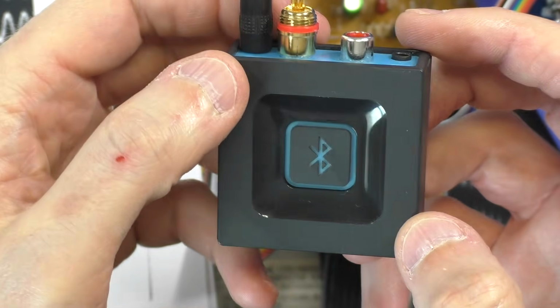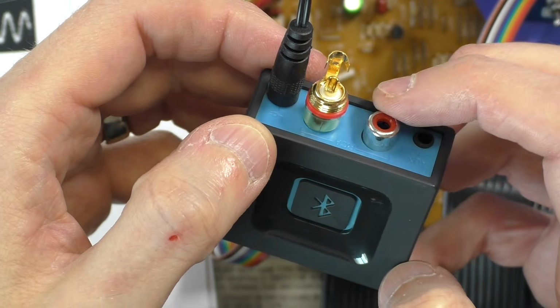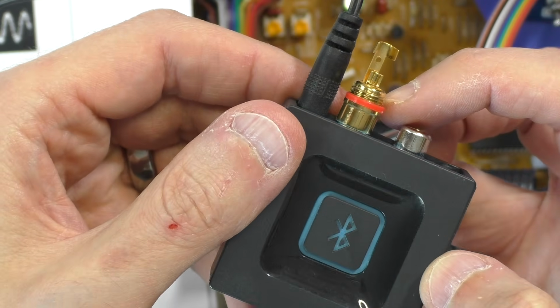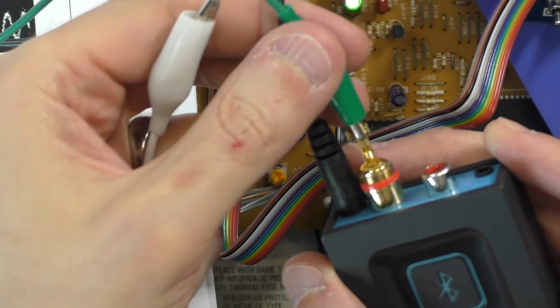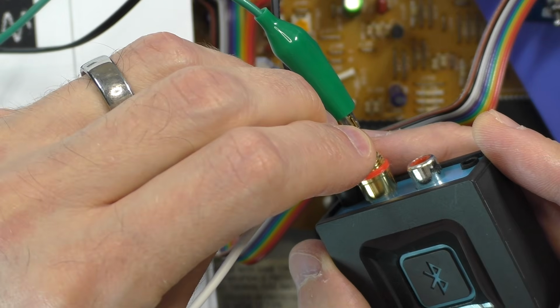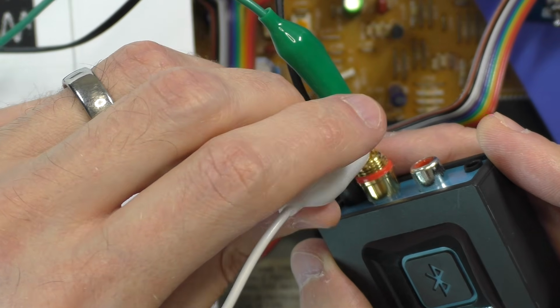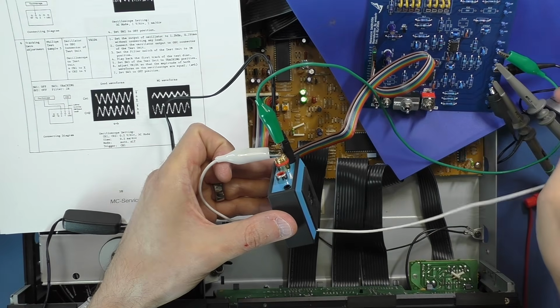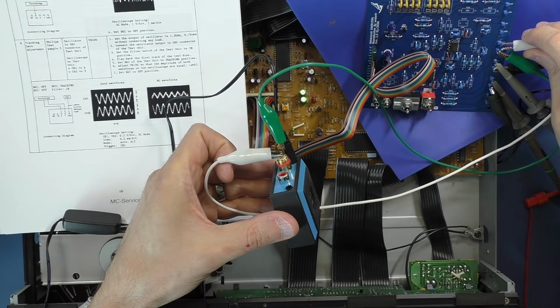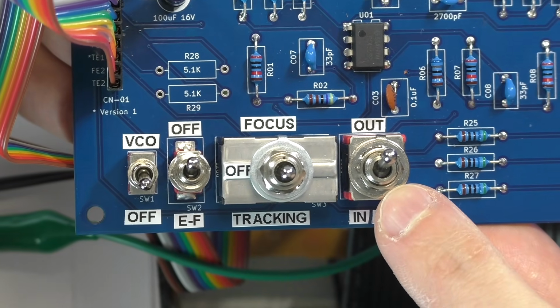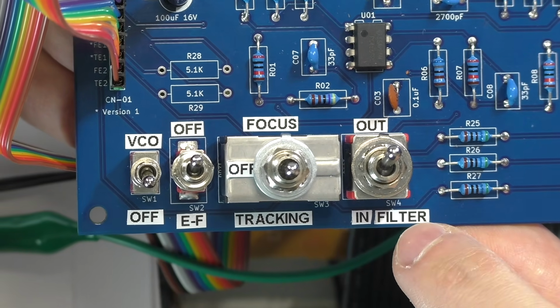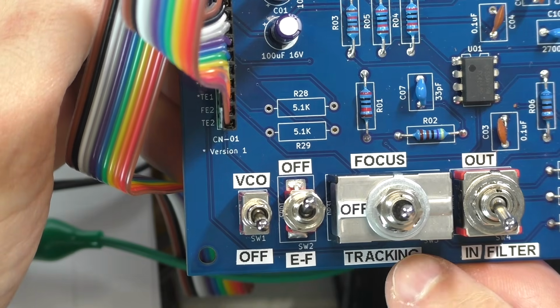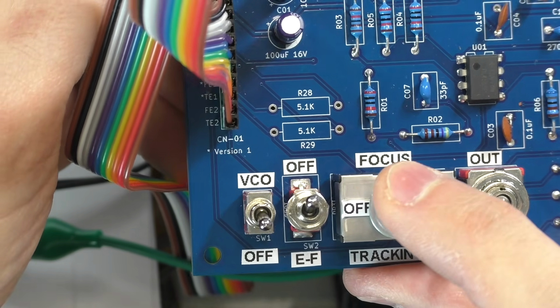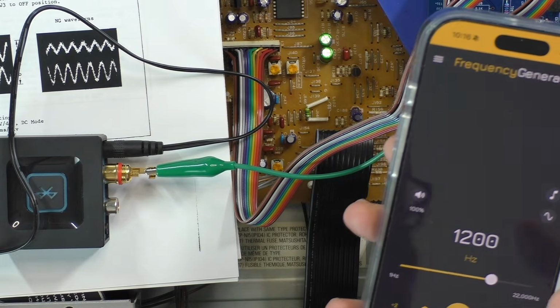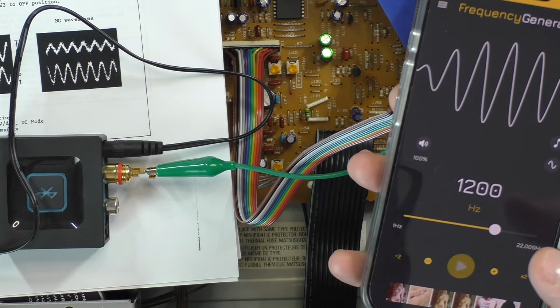I'm going to use this Bluetooth adapter, and I only need one channel, so I'm using this as a little breakout. So my ground wire goes there. I carefully connect the white clip to the center pin. Then I can connect these to the appropriate pins on the test unit. It says to set the filter switch of the test unit to the in position and set switch 3 to the tracking position. So with my phone synced to the Bluetooth adapter, I'm going to play the tone.